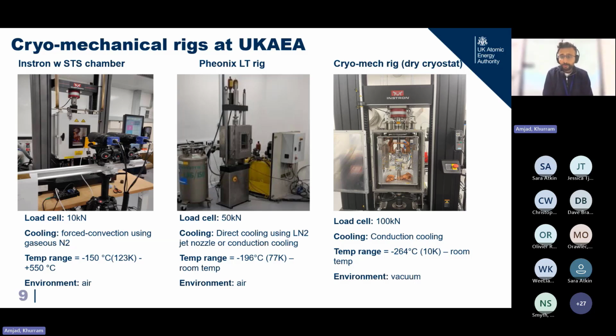And the third rig we have got has a 100 kilonewton load cell. It's a cryogen-free rig, which can go down to theoretically 10 Kelvin. It uses cryo coolers to cool the sample through conduction. And the environment is, of course, at such low temperatures, you can't do any testing other than in vacuum. And I have some preliminary results that I'll present from this rig as well.